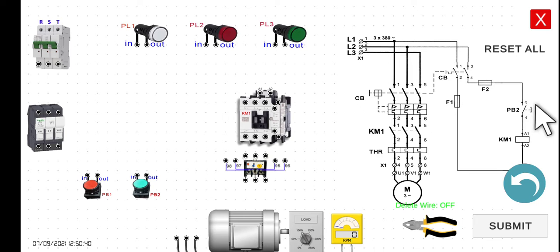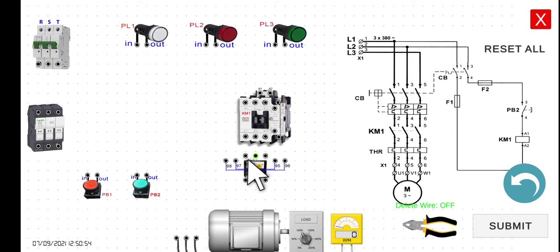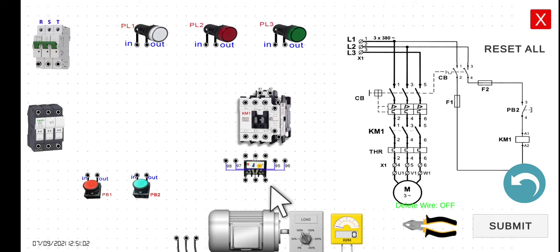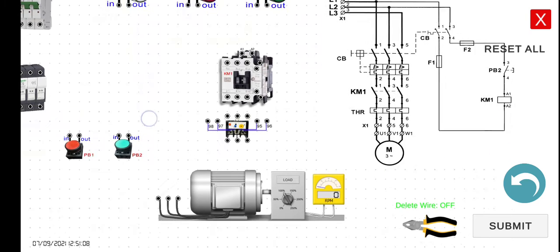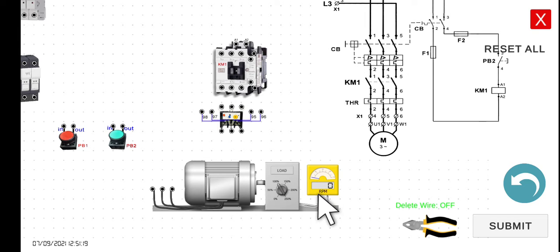This one is the normally open push button — normally open push button — which is labeled PB2. And then we have here K1, which is the coil of our contactor number one. And then we have here the thermal overload relay for the overload protection. So it means that if there is an overcurrent in our circuit or overload in our motor, this one will trip. And then this one is connected to a three-phase induction motor. As we can see, the motor is already running by listening at the sounds, and we can see the RPM value here.